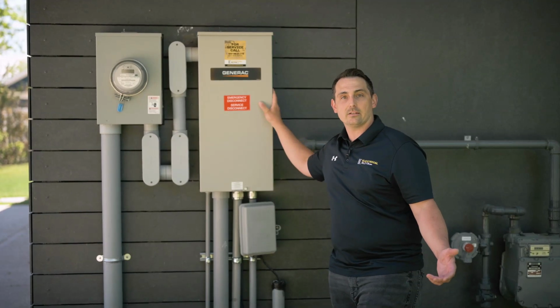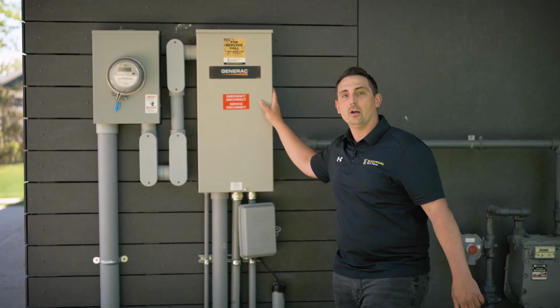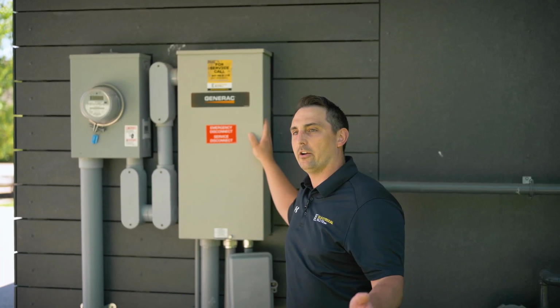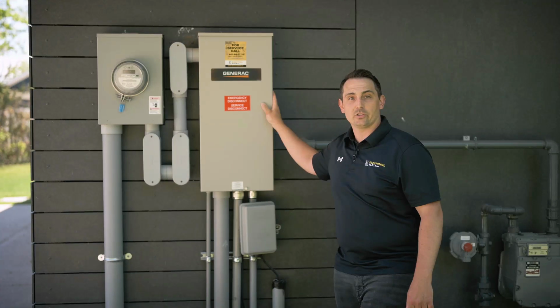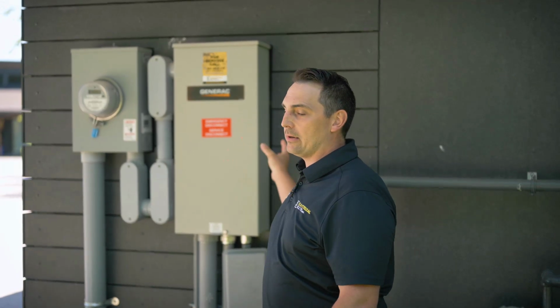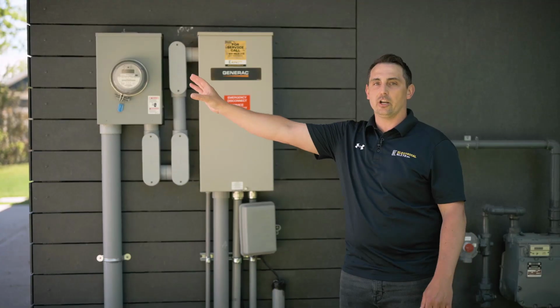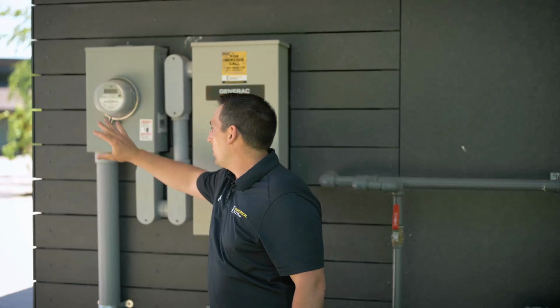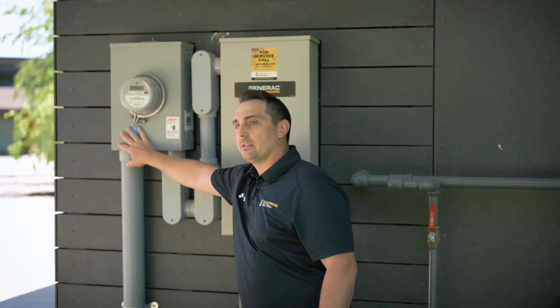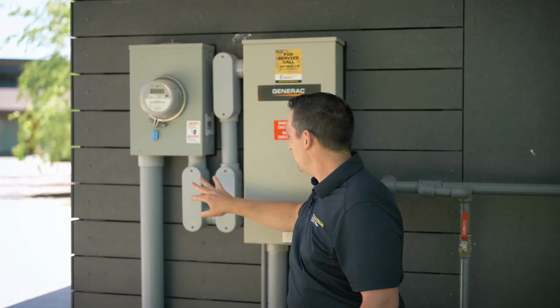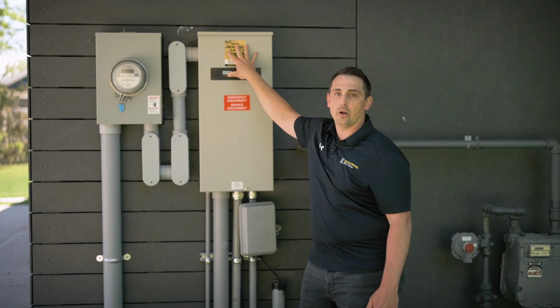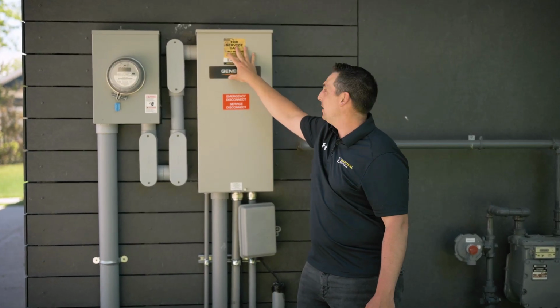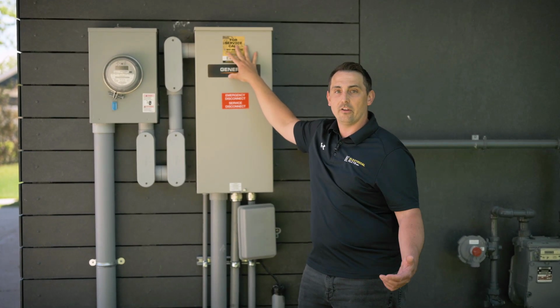This is the ATS. This is a 200 amp model, but they range from 100 up to 1200 amps for transfer switches. How they work, or the premise of them, is the power comes from the street, from your local utility provider, comes into your hydro meter base. From your meter base, it goes into the transfer switch.